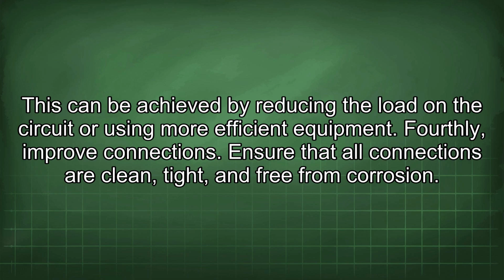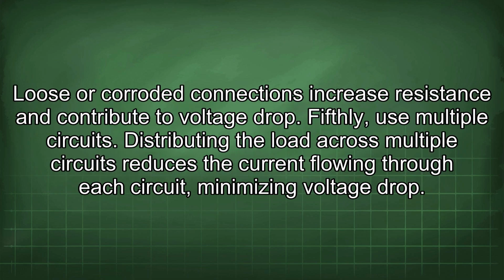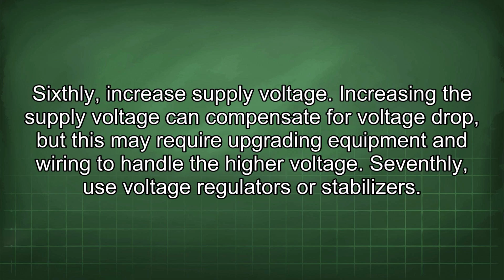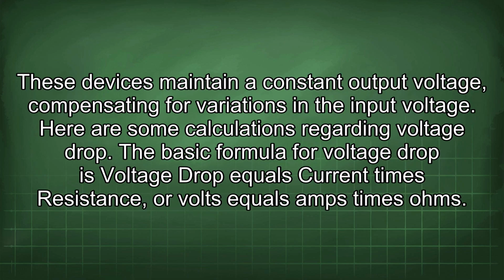Fourthly, improve connections. Ensure that all connections are clean, tight, and free from corrosion. Loose or corroded connections increase resistance and contribute to voltage drop. Fifthly, use multiple circuits. Distributing the load across multiple circuits reduces the current flowing through each circuit, minimizing voltage drop. Sixthly, increase supply voltage. Increasing the supply voltage can compensate for voltage drop, but this may require upgrading equipment and wiring to handle the higher voltage. Seventhly, use voltage regulators or stabilizers. These devices maintain a constant output voltage, compensating for variations in the input voltage.